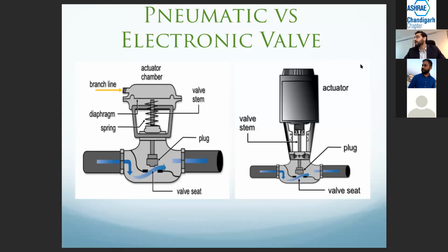And now in this case, the actuator is sent a 0 to 10 volt signal, for example. And if you say, hey actuator, this is 50%, it'll precisely close it by 50%. There are also end devices which we can use on the actuator, which give us feedback on how much the actuator ended up closing by the end of the motion, and give us an understanding of the system's flow rate, etc.